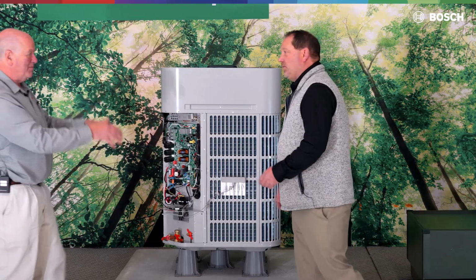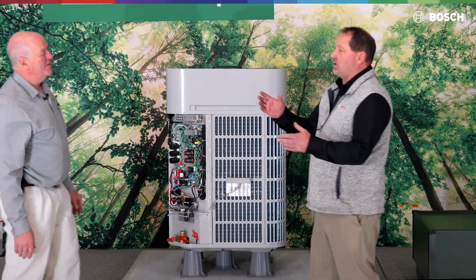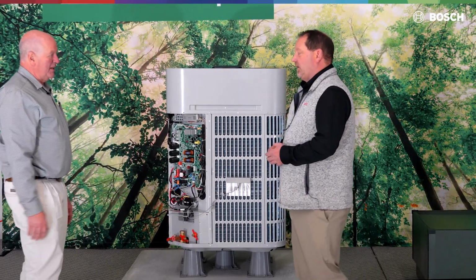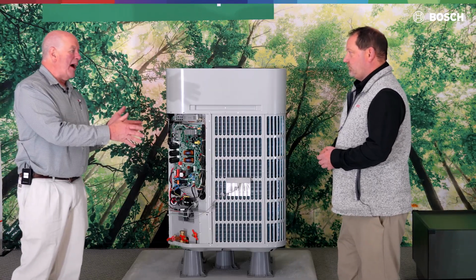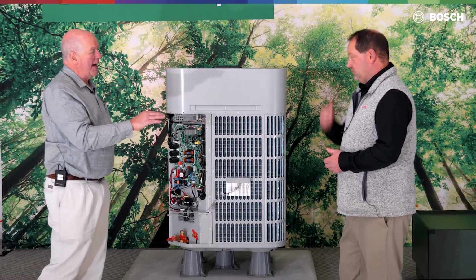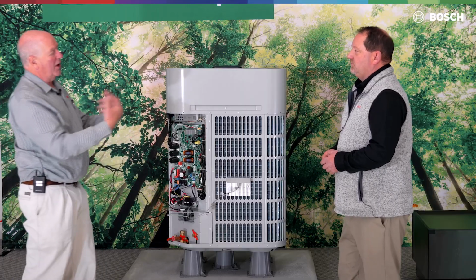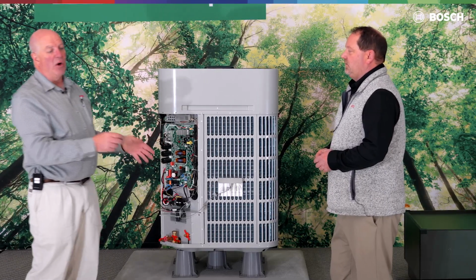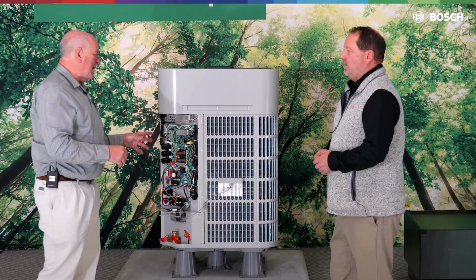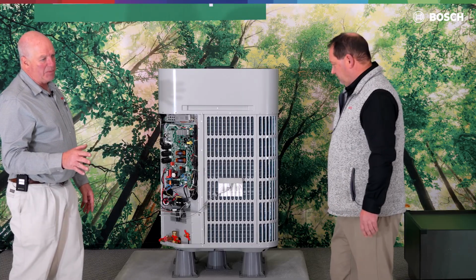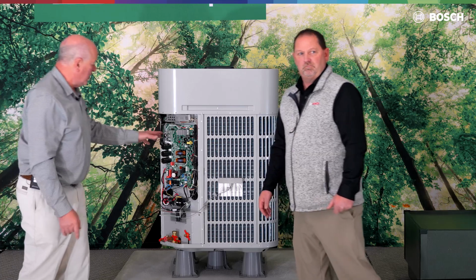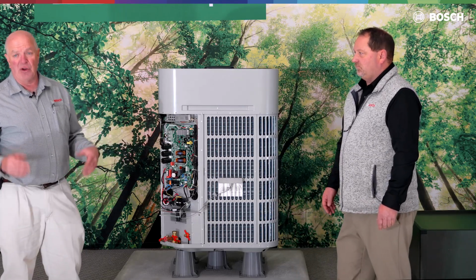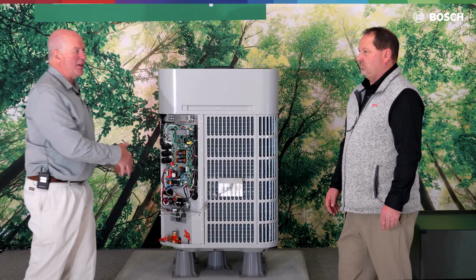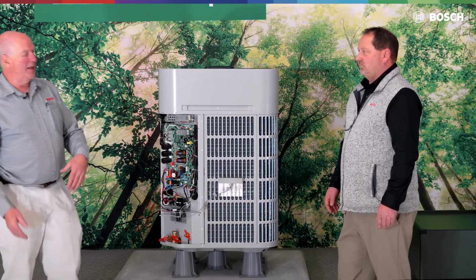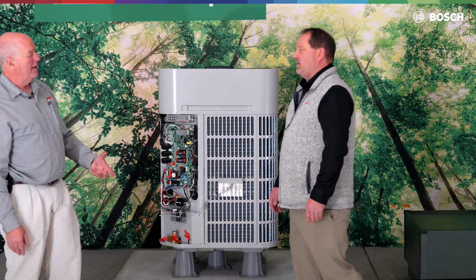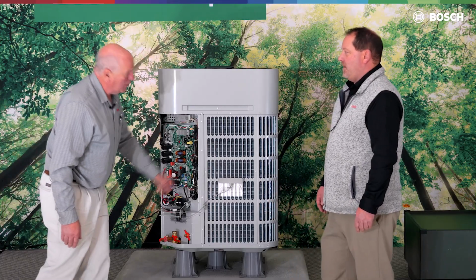I don't want to mention names. You mentioned surge suppressor, but we're also talking about surge protector, right? Correct. It does both. And we want something that has a permanent lockout. So if a problem occurs, it's going to shut down the system, the homeowner has an issue, and they're going to call you out saying, hey, my unit's bad. If you don't have something with that permanent process, then it can reset. On most surge suppressors, when it goes the first time, the unit will continue to run, but you've lost your protection. If you lose your protection, the second surge takes out the compressor. Now the homeowner's kind of bummed that they bought a surge suppressor that didn't do its job. It did its job, but that means they have to go out daily looking for that light sensor.